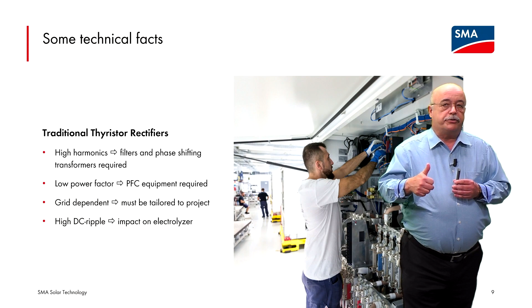At partial load, which you quite often have with renewables, systems generate a high DC ripple, which reduces the lifetime of the electrolyzer and also reduces the efficiency.